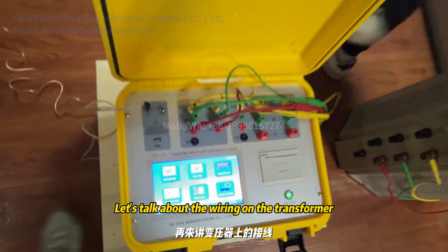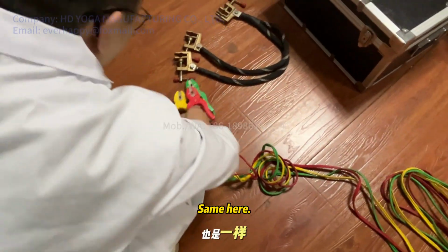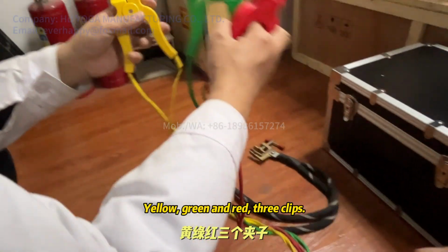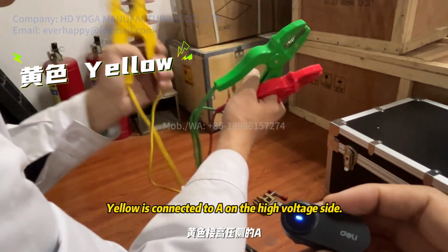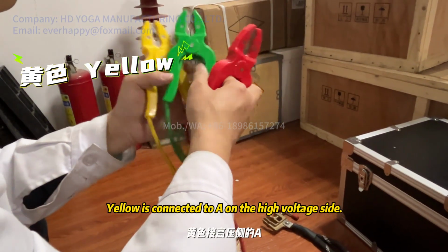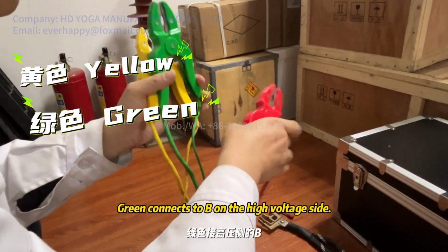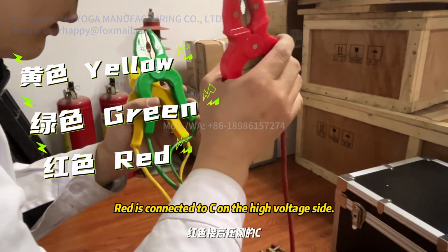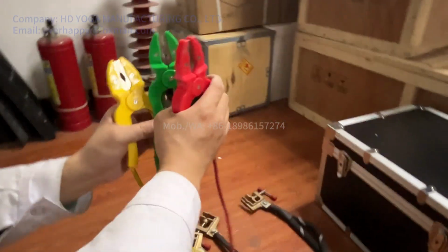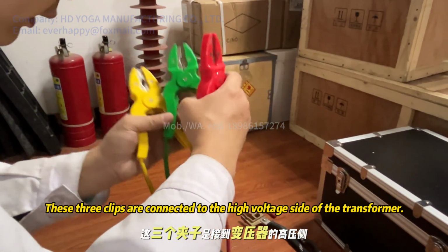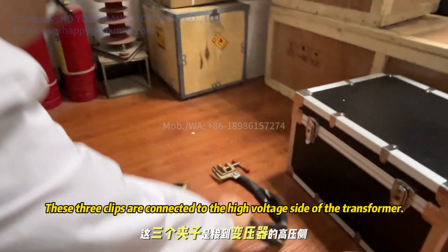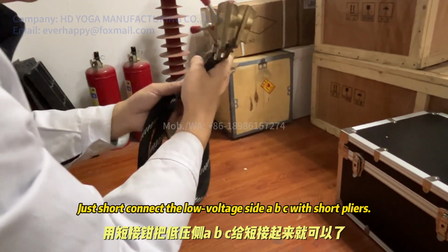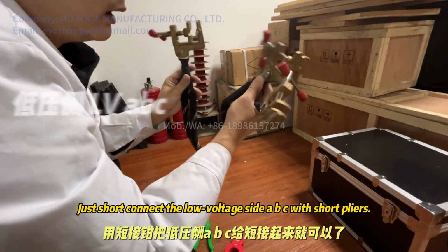Let's talk about the wiring on the transformer. Same here. Yellow, green and red, three clips. Yellow is connected to A on the high voltage side. Green connects to B on the high voltage side. Red is connected to C on the high voltage side. These three clips are connected to the high voltage side of the transformer. Just short connect the low voltage side ABC with short pliers.